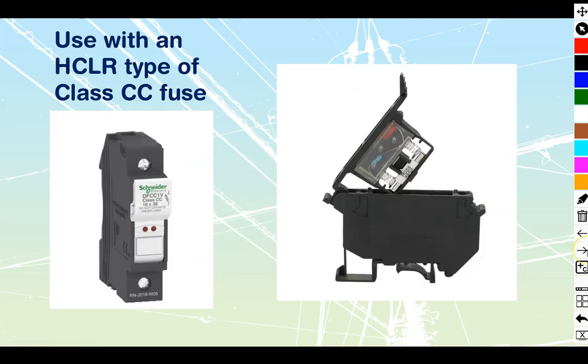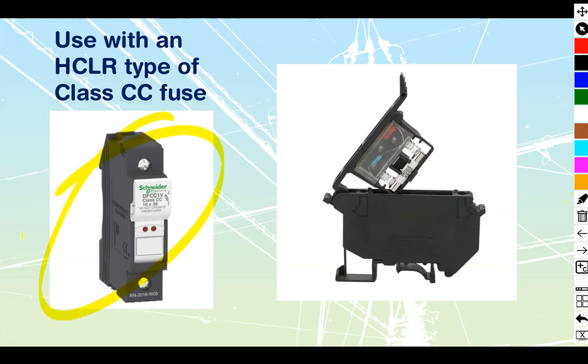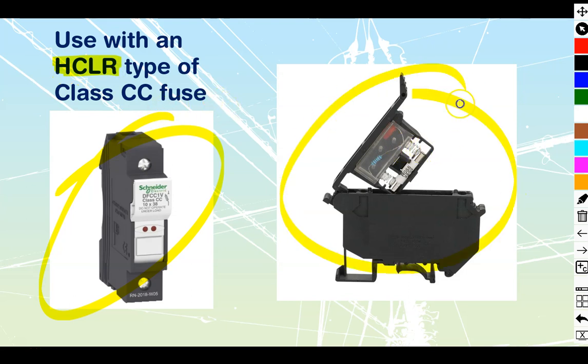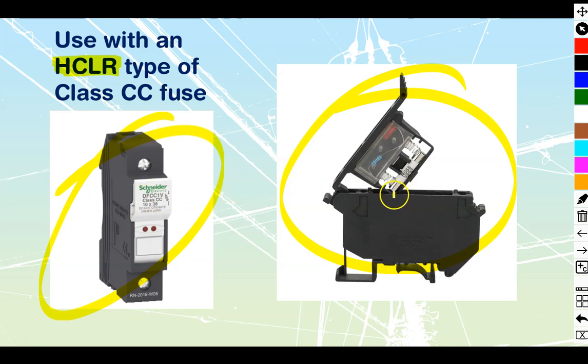Let's take a look at how this looks practically. Before we do, we'll just take a quick look at your options for fusing. I suggest going one of these two routes. You can either use a class CC fuse. These are going to be a 10 millimeter diameter fuse. Fairly easy to get a hold of. If you do get them, get the HCLR, which are going to be the fastest acting fuse inside of that family. Or, alternatively, you can go with one of these, which is going to be one of those narrow glass or ceramic style of fuse holders. Both of these fuse holders that we see will mount onto DIN rails, so you can keep them inside of your PLC cabinet close to where your PLC inputs themselves are. We will be using this one in our drawings.